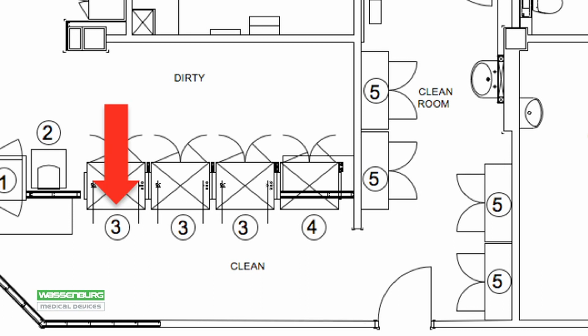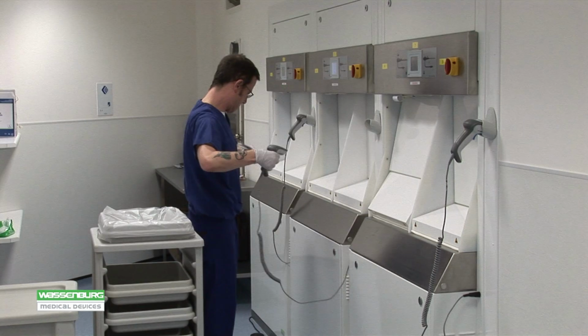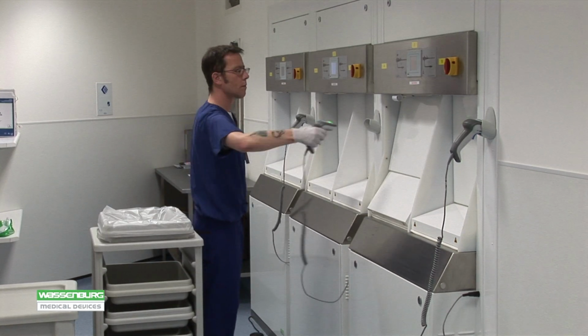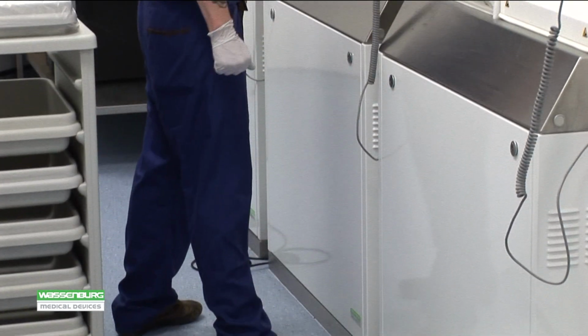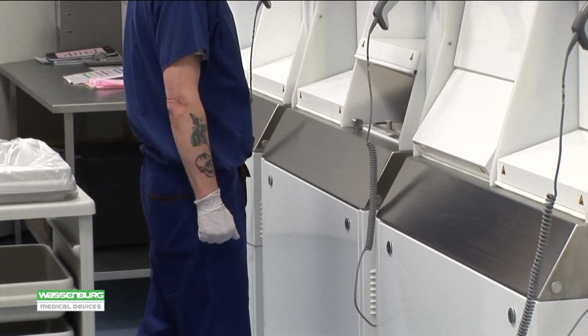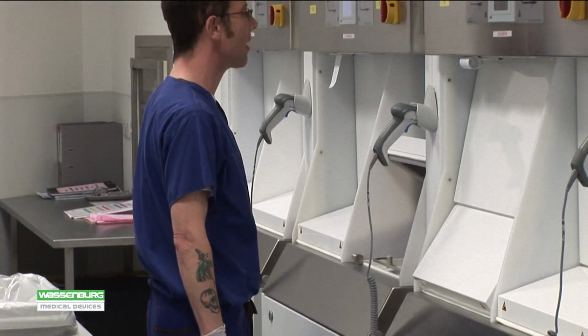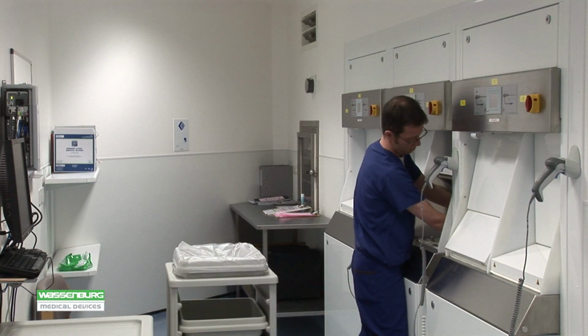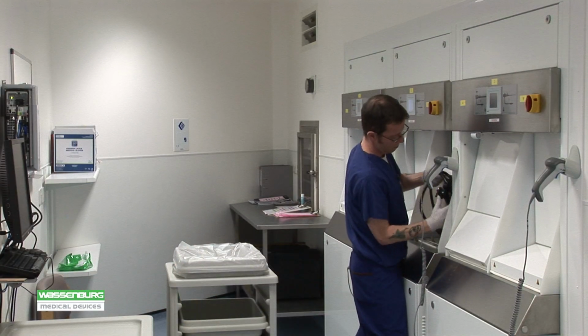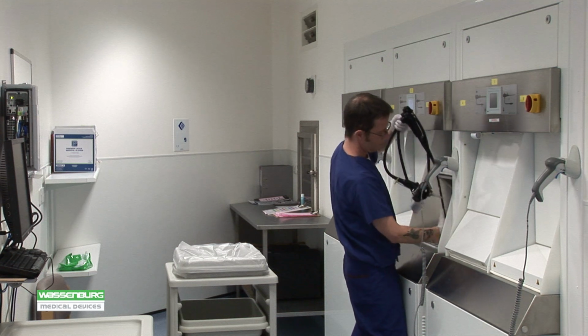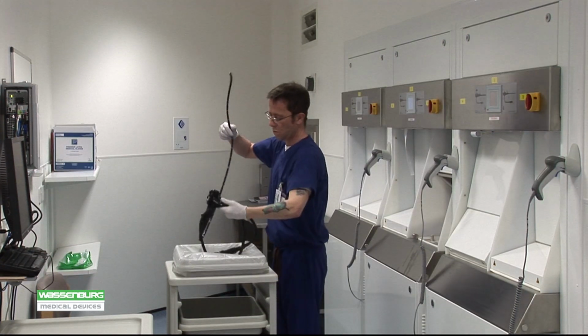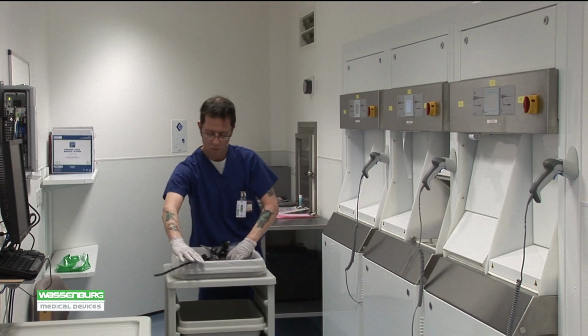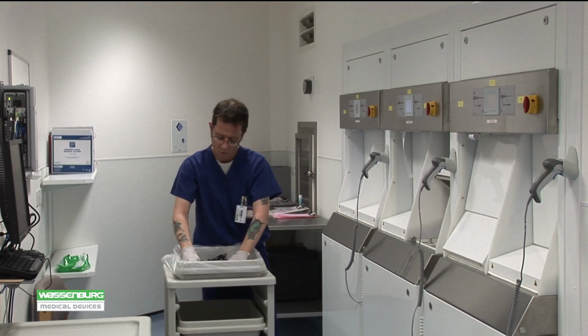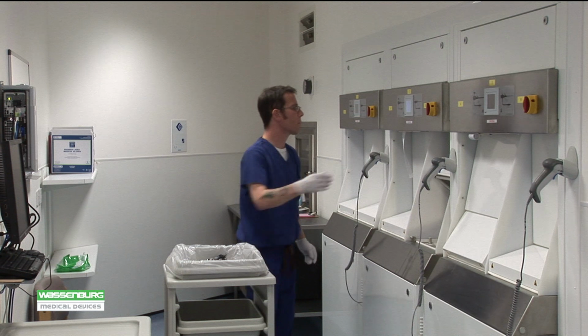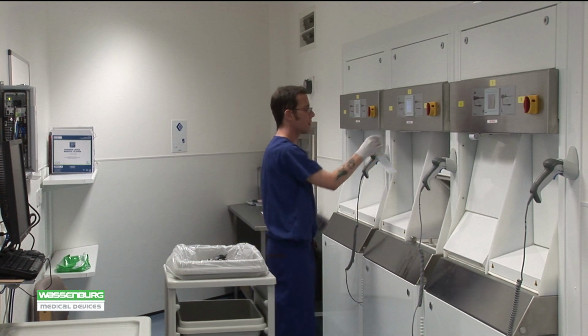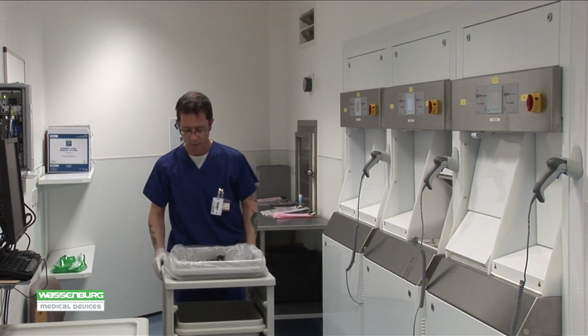When the cycle is finished, the operator scans their identification badge to complete the process, and all cycle data is downloaded to the server. Lid opening is hands-free using foot pedals, preventing the need to touch the outside of the machine. A printout is produced, listing details of that scope process that will be returned with the scope to the treatment room or DRY300 storage cabinet to form part of the overall tracking system.